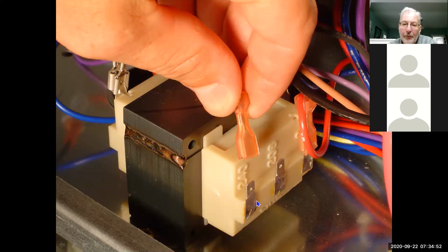What happens if you don't move the wire to the proper voltage? They come set for 240. If you put it on a 208 system, what's going to happen is you're going to have low voltage, 21, 22 volts. And since this board really looks for ground circuits and it looks for resistance values, it could throw things off and it may not work properly. It may give you some nuisance faults. So again, make sure you get the proper tap here for the proper voltage.